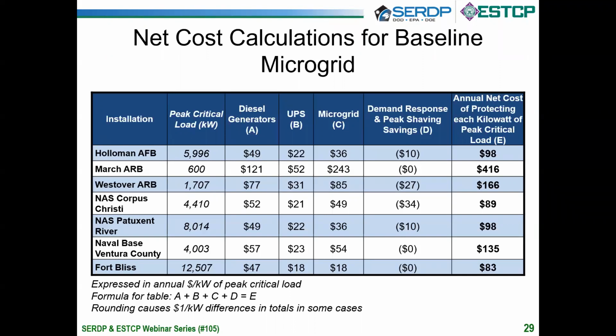Now in this chart, you'll notice differences in the costs and savings between the installations. March Air Reserve Base has a total baseline microgrid cost of $416 per annual kilowatt, while Fort Bliss is 5 times lower at $83. Most of the reason on the cost side is scale. March is only protecting 600 kilowatts of critical load. You'll see that in the second column from the left. While Fort Bliss is protecting 20 times as much critical load. It's important to remember that many of the costs of a microgrid are fixed and do not vary with load. So Fort Bliss enjoys economies of scale on that part of the costs, as well as on some of the generators and UPS.